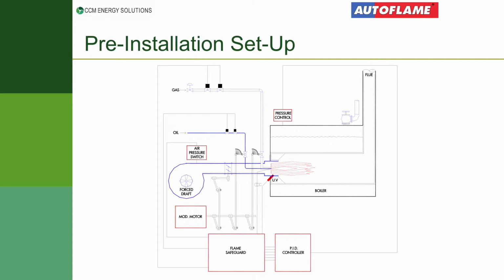If we take a typical pre-installation setup on a site, and this is a standard burner, you have one modulating motor here controlling your cams and jack shafts and your gas valve. That's one motor controlling that gas and air, which means you can never have optimum combustion. You have a completely separate black box, a burner safety box mounted in the panel, a completely separate proportional integral derivative controller and pressure sensor. If it's a steam boiler, you'll have a completely separate water level controller. If you're looking at multiple boilers, you'll have another box that does your lead lag control.